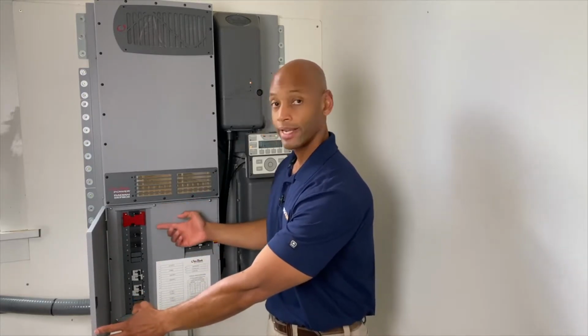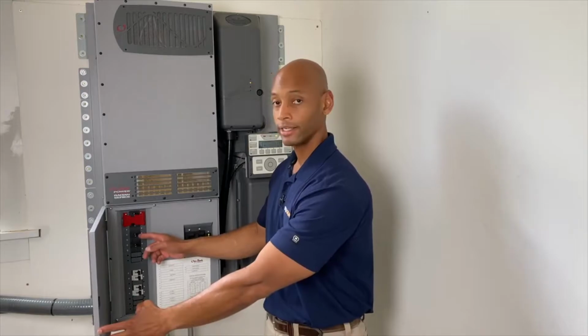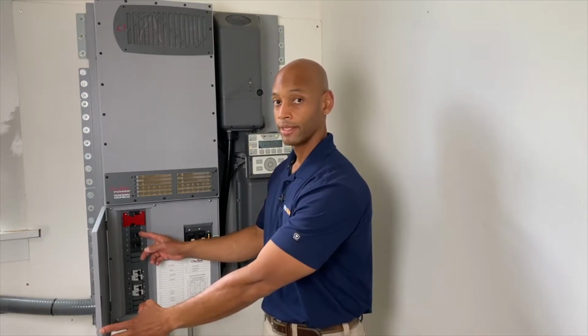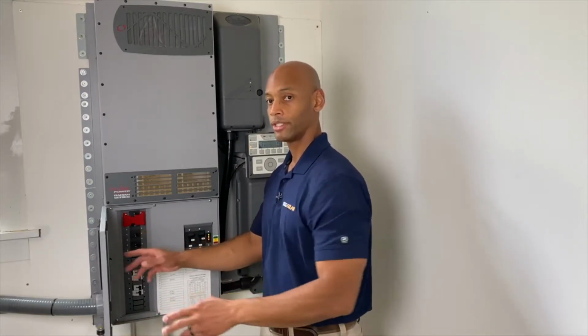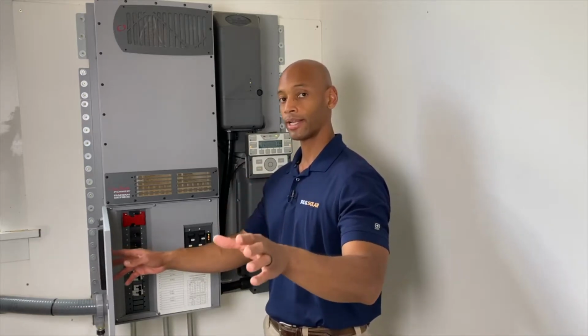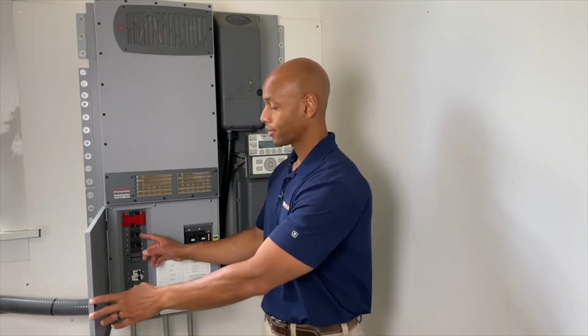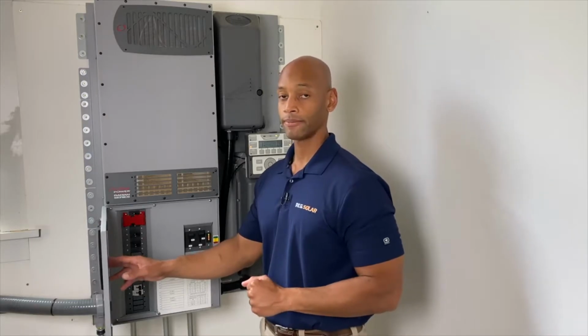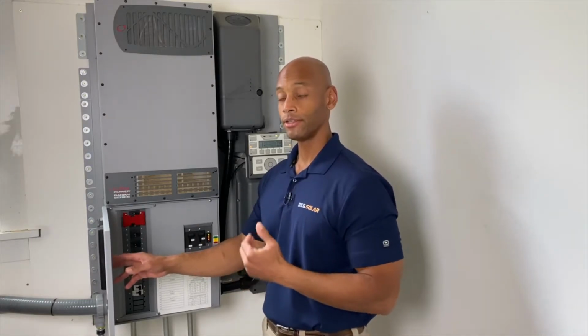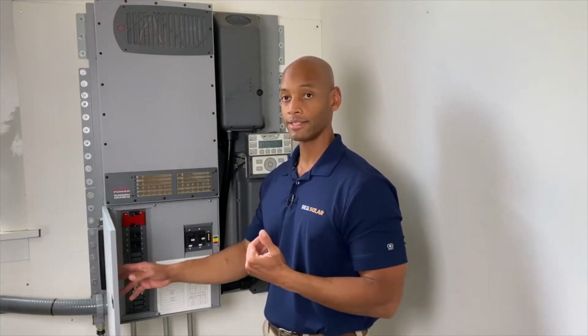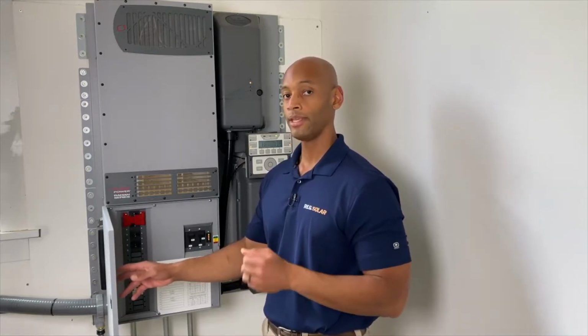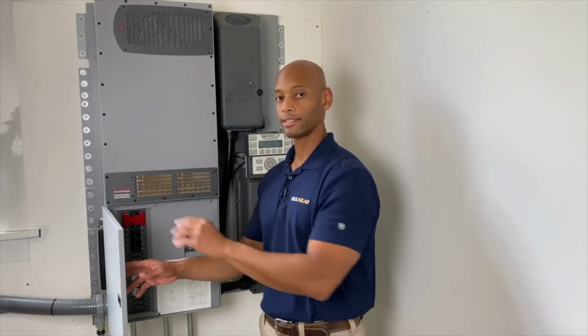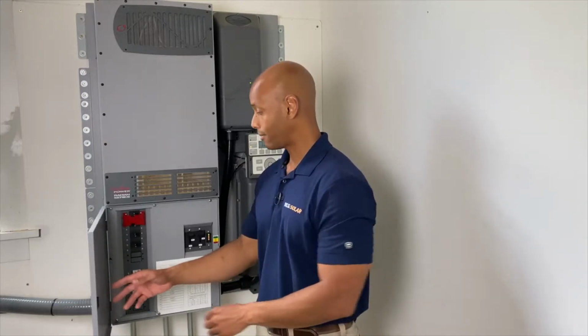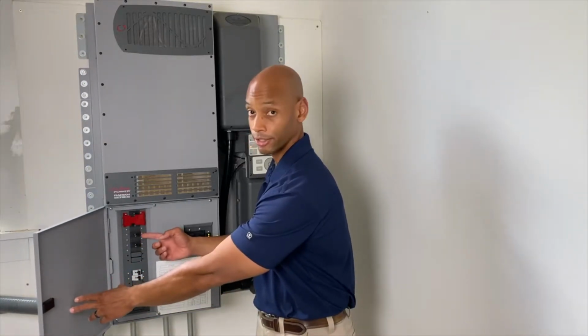Okay, working our way down here, the next connection is the utility grid input. This is the output circuit. Once the critical load circuits are powered inside the house, this is your connection out to the utility grid. This is a bidirectional circuit. You can pull power in from the grid as needed to help power loads at nighttime, and you can also export the excess solar power to the power company. That's all done via this second circuit breaker here.